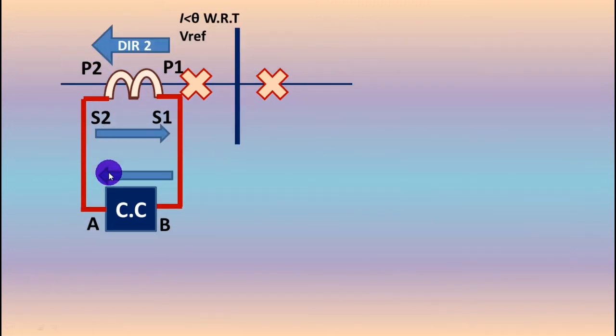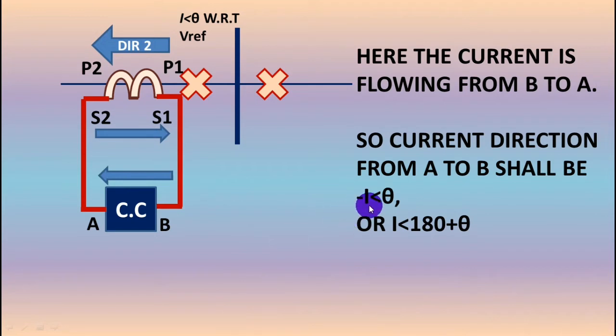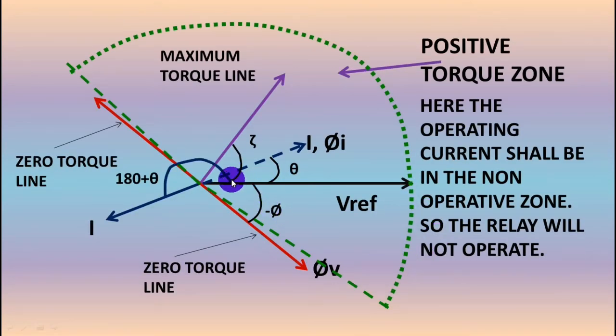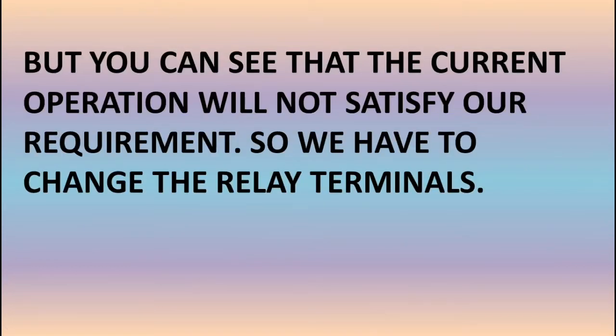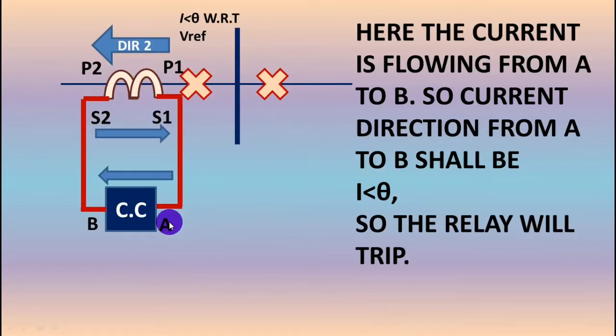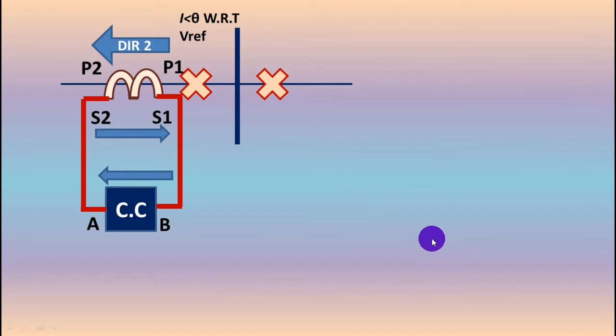So we see that for direction 1 it is generating positive torque, which means for direction 2 it will not generate positive torque. The connection is the same, but the current is flowing in the other direction, so here the current will flow from B to A. The value from A to B will be minus I theta, or 180° plus theta. Plotting it in the phasor diagram, this becomes 180° plus theta with respect to V reference — the current is lying in the negative torque zone, so the relay will not operate. Our desired operating condition is not achieved. We have to alter the relay terminal. By simply swapping terminals A and B, for direction 2 the current flows from A to B, so the relay will trip — and for the other case, the relay will not trip.